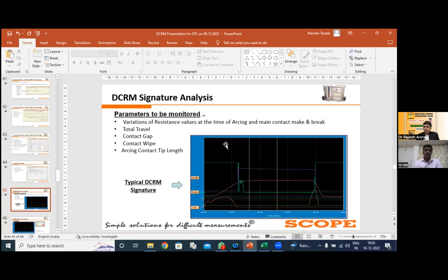As all of us know, at the time of arcing, a tremendous amount of heat is generated at that point, and because of that your contacts may get deteriorated or damaged. To overcome that, the contacts are coated with tungsten alloy or chromium alloy, which have a higher temperature coefficient, and it will save your contacts. So on your screen, the typical DCRM signature is there.